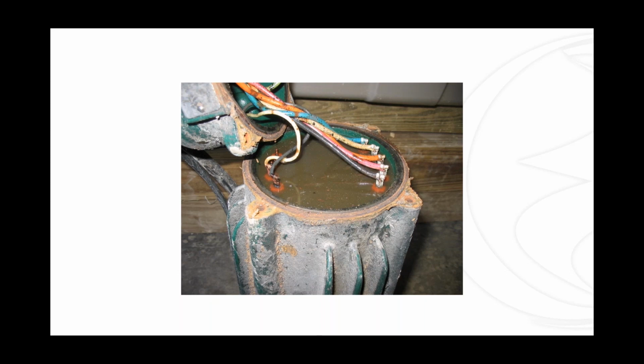People typically think that their pump is bad. It may or may not be. But again, just by not using a cord grip, this was a silly and very expensive mistake. So good news is that all Zoeller pumps are built so that if this should happen, it might be just the power cord, might be the cap and cord assembly, but you can replace it and fix it, and you could put this pump right back in service. So again, make sure you use cord grips.